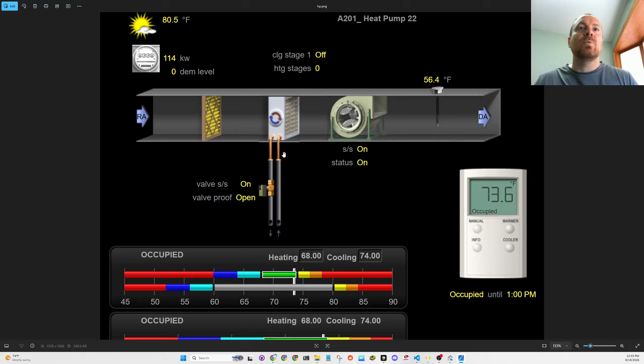It's even, in the right conditions, higher efficiency than a natural gas boiler. This is part of the pumping system that pumps water through their geofield. This is in the middle of summer, so some of these numbers they pull out of the well are 60-degree water that they use to make cooling in the summer. In the winter, it dips down into the 40s. So they pull all the heat out of the ground, and in the summer they reject all the heat back into the ground.